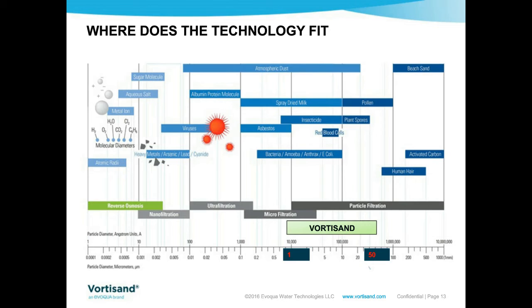So Vortisand cross-flow microsand filtration fits somewhere between conventional media filtration and microfiltration. Essentially, it fills the gap between multimedia filters and membranes. Vortisand will capture particles between 50 and less than 1 micron, but the sweet spot really is where other filters have challenges, in the sub 10 micron, sub 5 micron range.